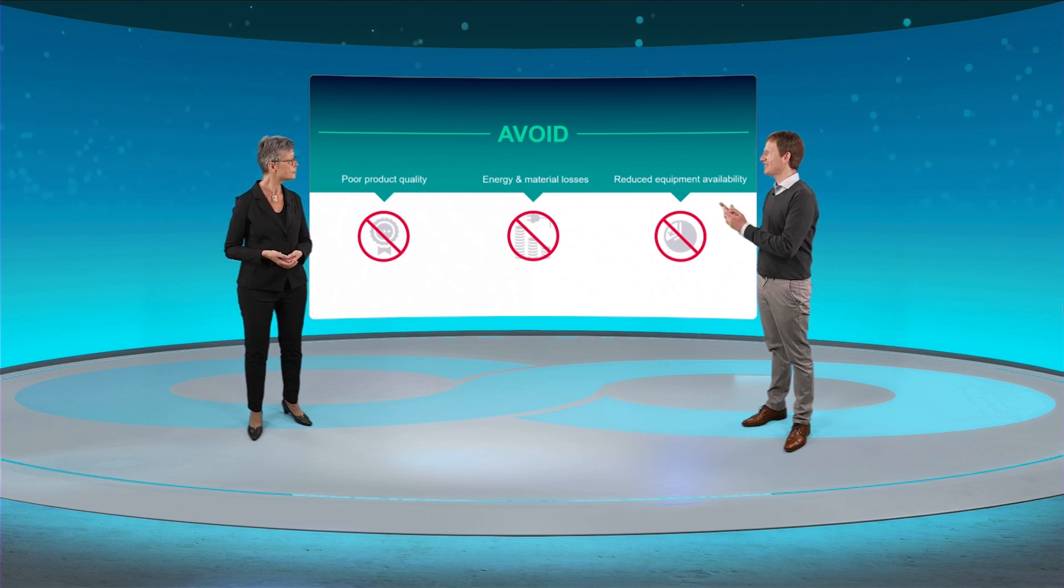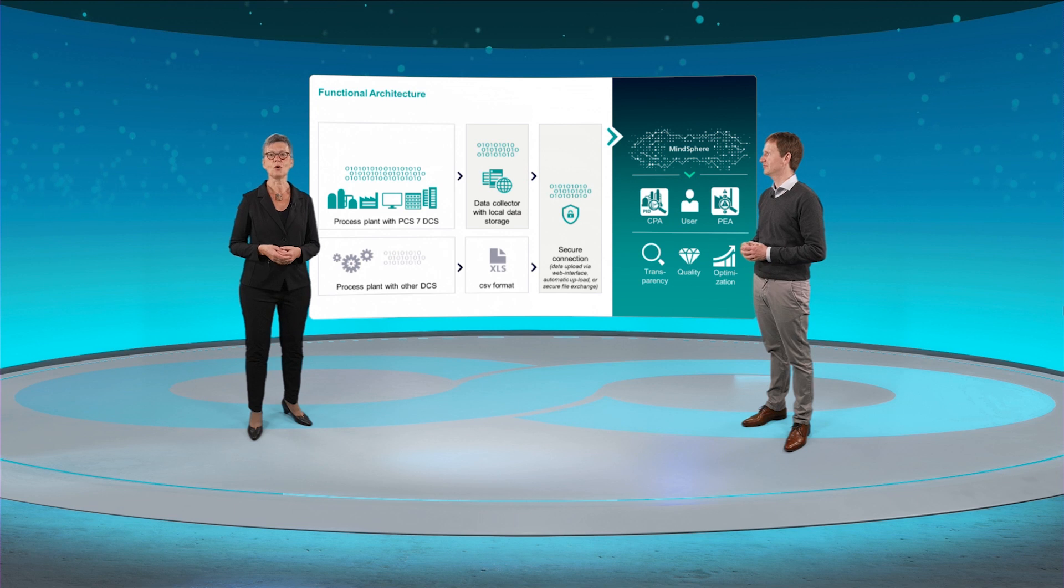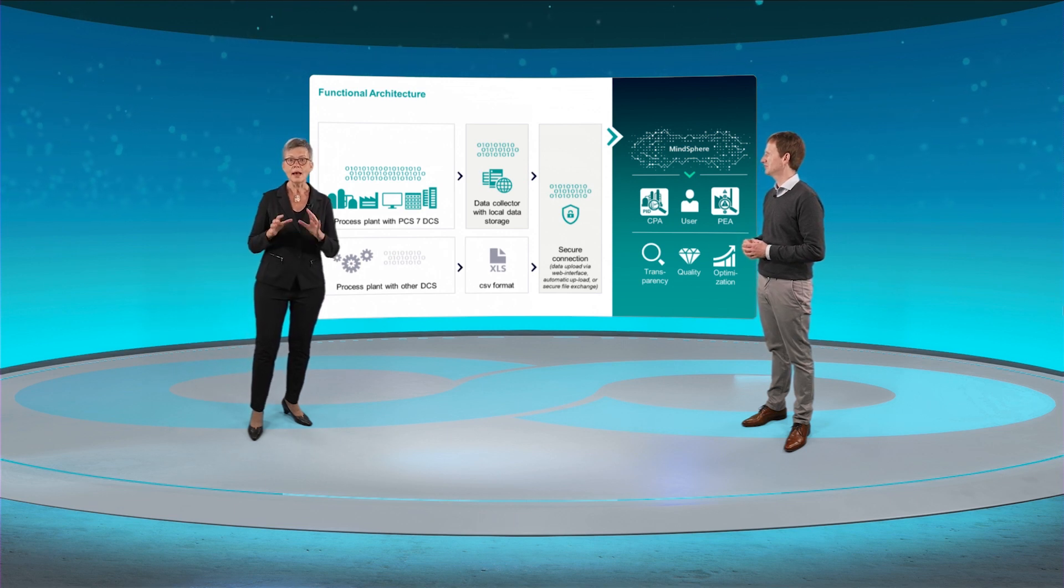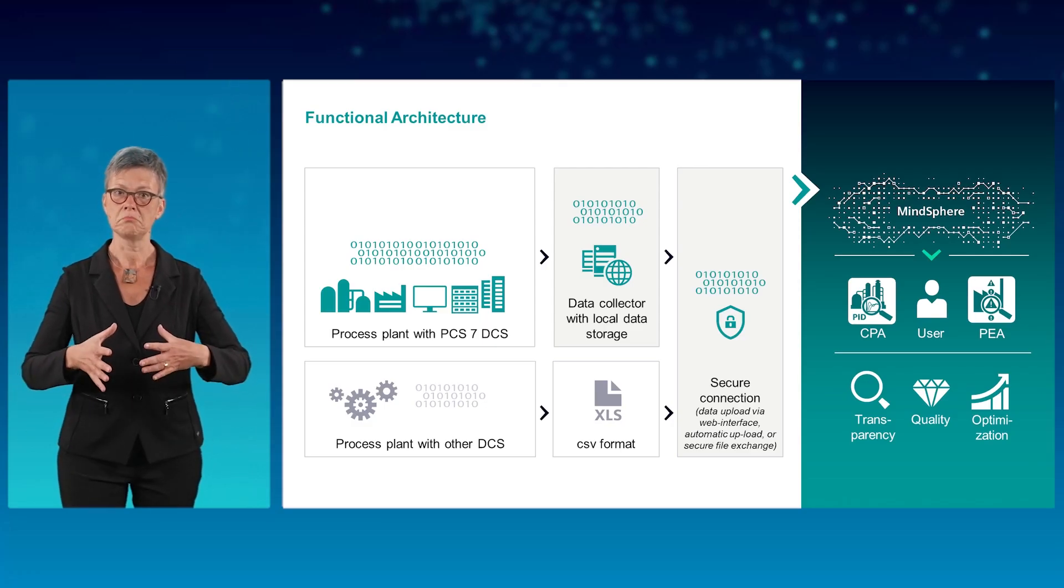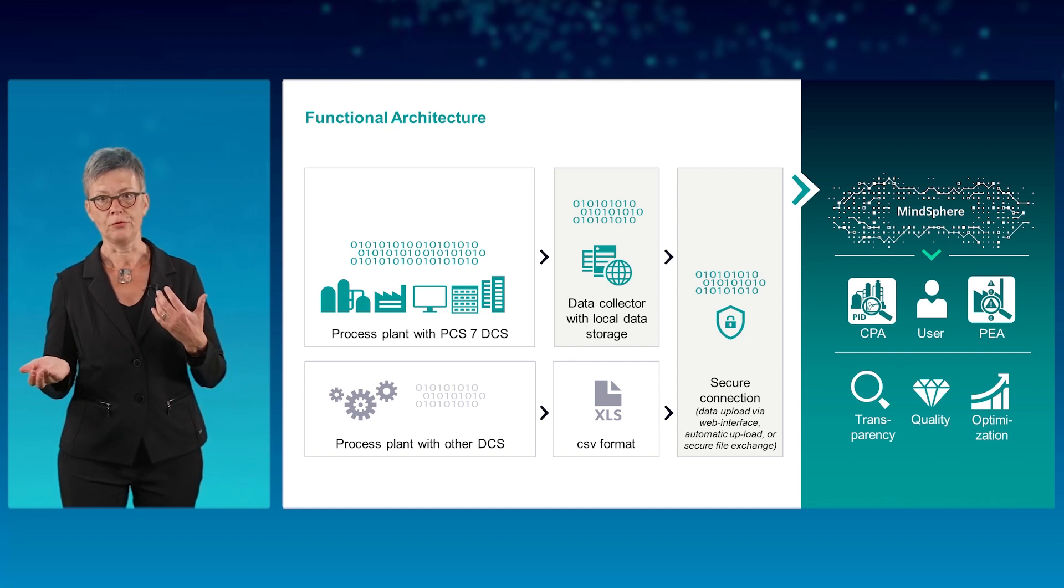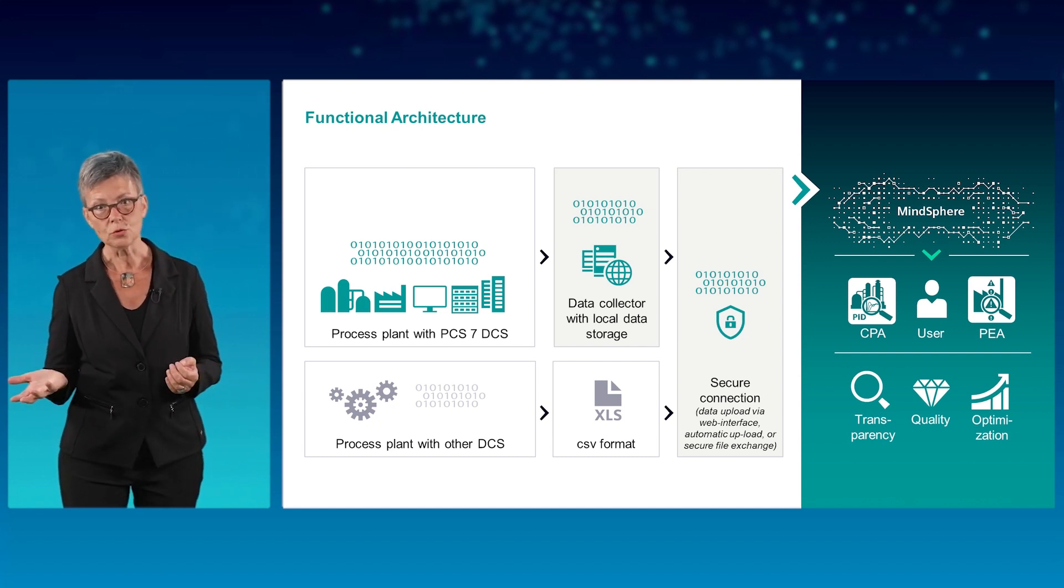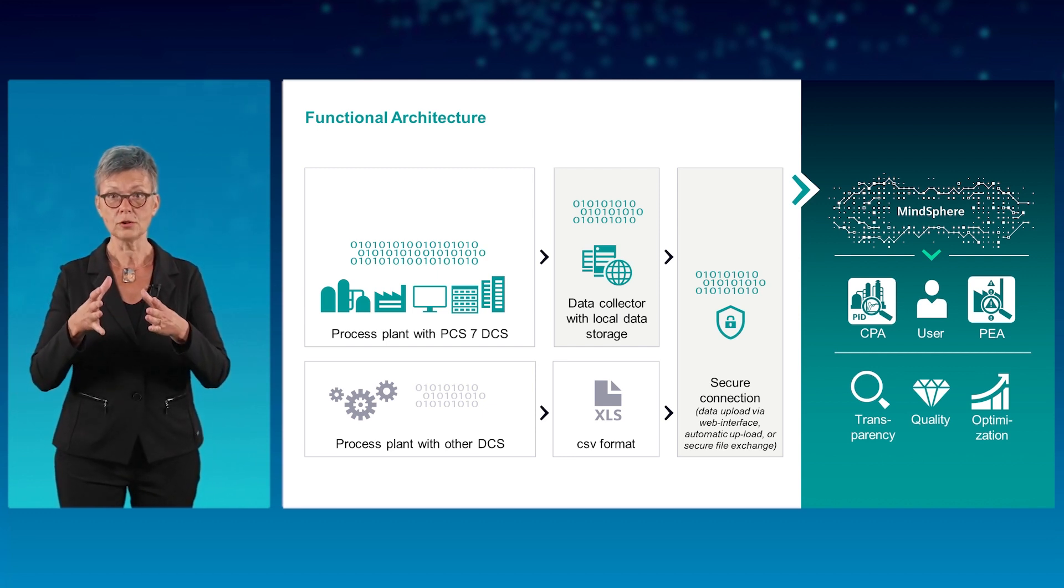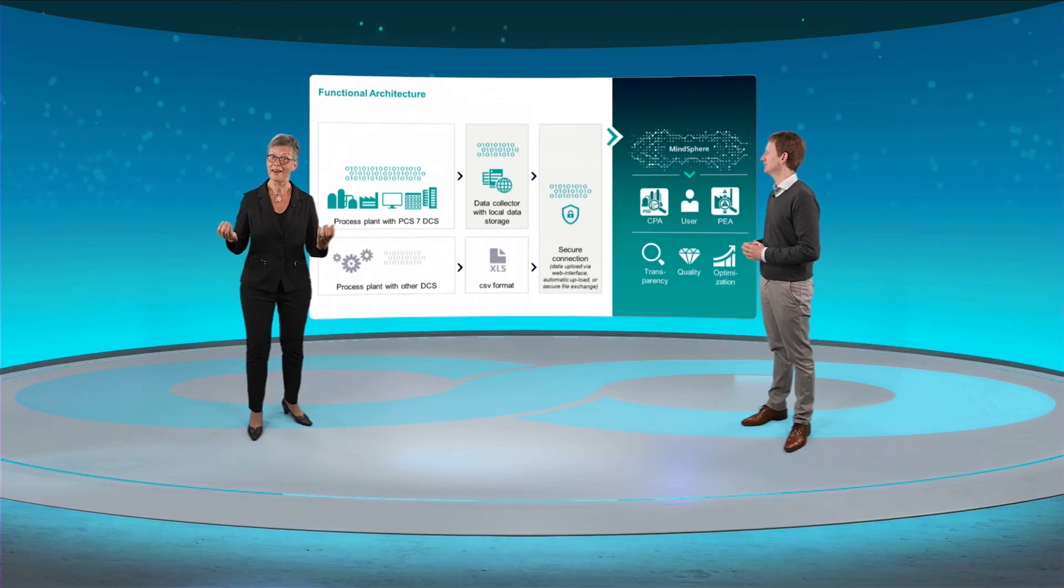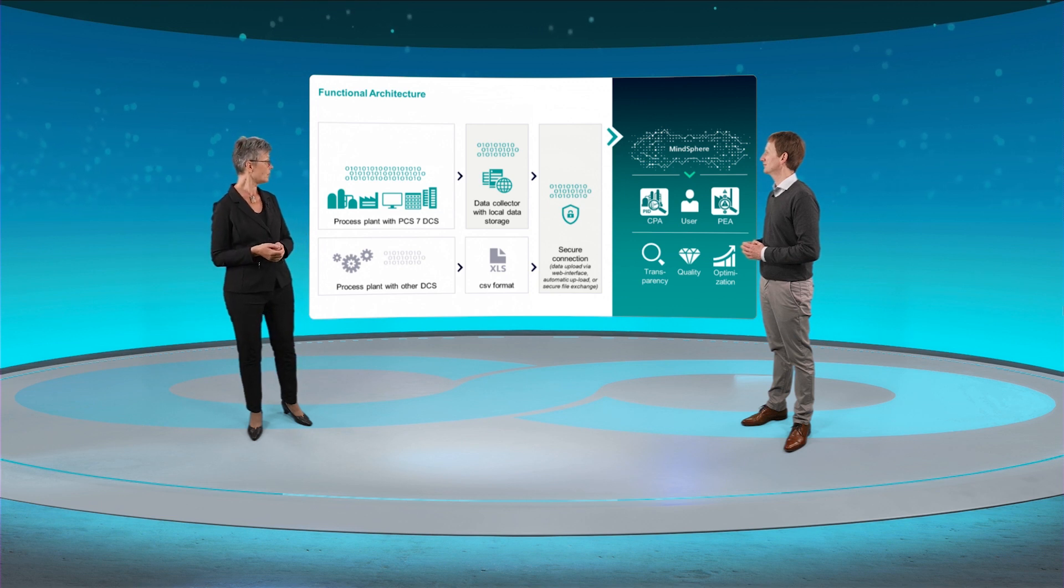I see what you're getting at. Let's stick with the analysis of control loop performance. A small piece of software, the so-called data collector, collects data from the DCS, PID parameters, values of the controlled and manipulated variables, set point values, and so on. And this data is uploaded by a secure connection to a secure cloud. It is analyzed using simple AI and the results are provided by an interactive web interface.